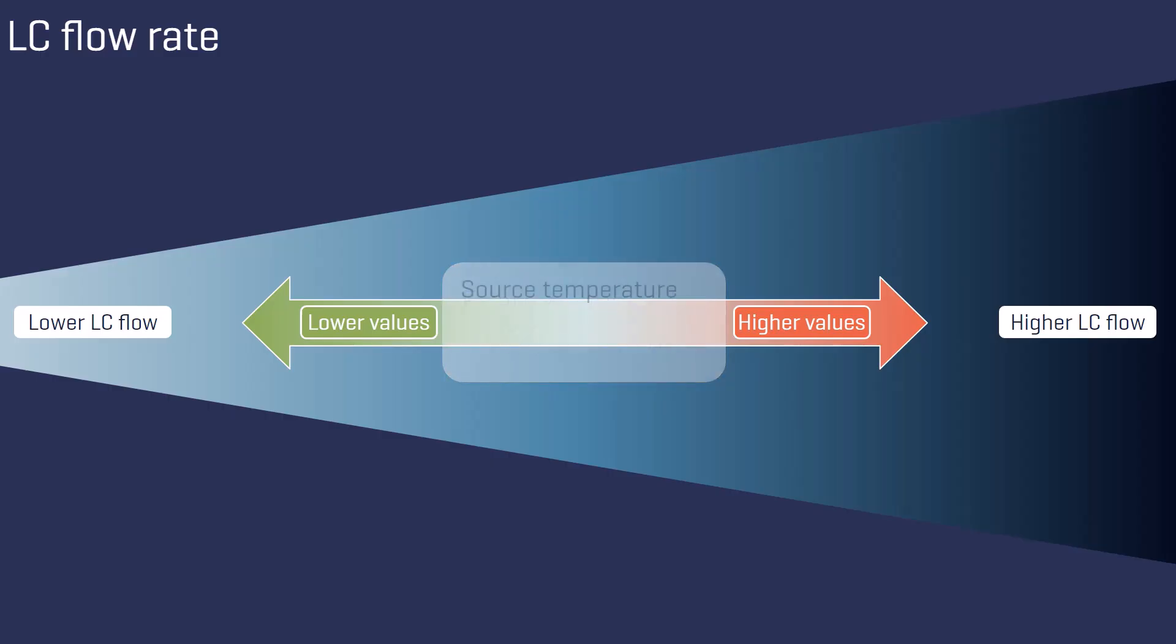Consequently, the optimal values for the source temperature and the ion source gases 1 and 2 tend to be higher at increased flow rates. In addition, the curtain gas pressure must be increased at higher flow rates to effectively prevent larger remaining droplets from entering the mass analyzer.